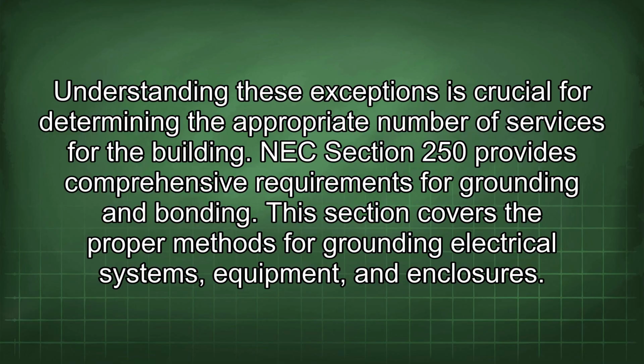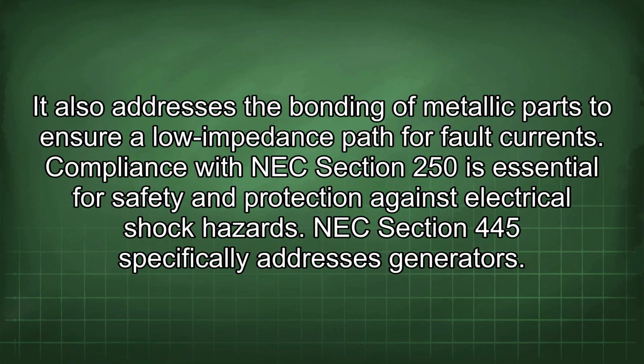NEC Section 250 provides comprehensive requirements for grounding and bonding. This section covers the proper methods for grounding electrical systems, equipment, and enclosures. It also addresses the bonding of metallic parts to ensure a lower impedance path for fault currents. Compliance with NEC Section 250 is essential for safety and protection against electrical shock hazards.